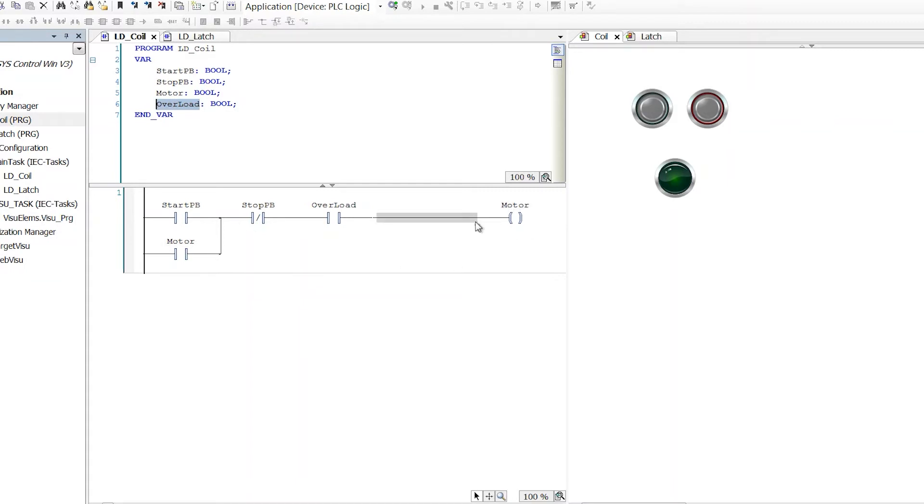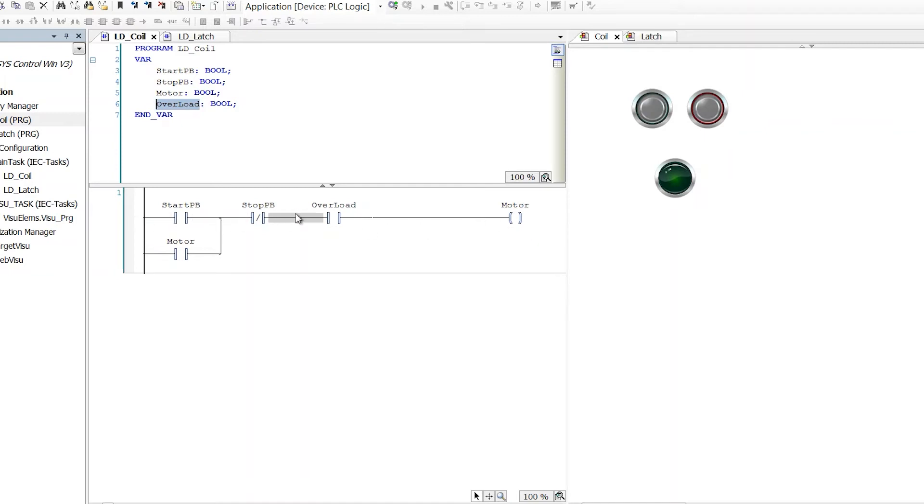So the standard coil in ladder logic is turning on if these conditions are true, and it's turning off if these conditions are not true. So if this circuit isn't complete from left to right, this function is still active. It's actively writing a zero or a false or an off to this bit here.